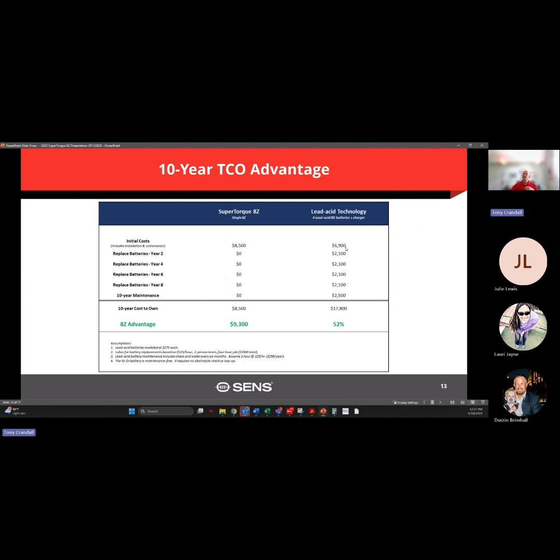So what you're seeing is the initial installation of a lead acid setup at $6,900, and then every 2 years, based on NFPA requirements, a $2,100 replacement cost. Once again, with these values being so conservative, these numbers are likely higher.